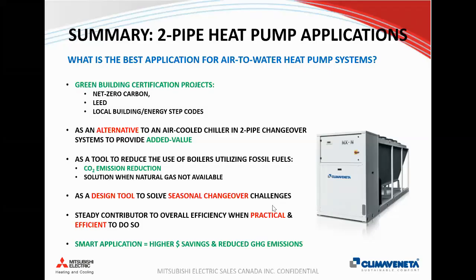But really, anytime you want to reduce CO2 emissions and anytime you want to use less natural gas, air to water heat pumps is one way to go if you're designing systems with boilers. But again, don't think of the heat pump as a silver bullet or a magic box that's going to solve all your problems at all times. Think of it as a steady contributor to overall efficiency for the building when it's practical and efficient to do so, whatever that means to you.